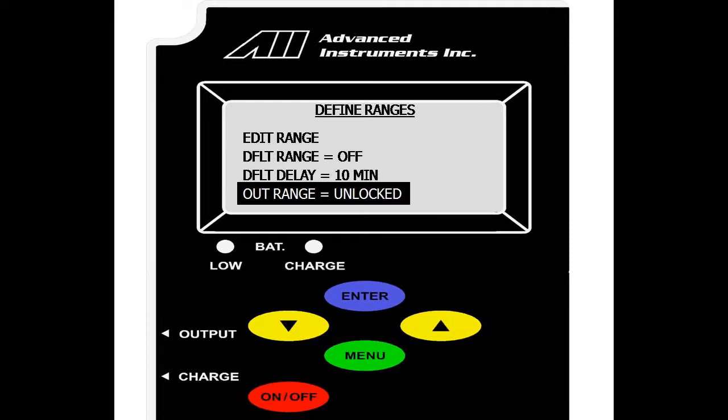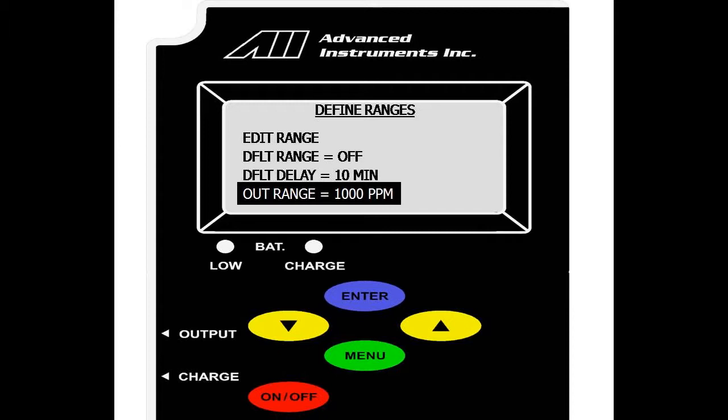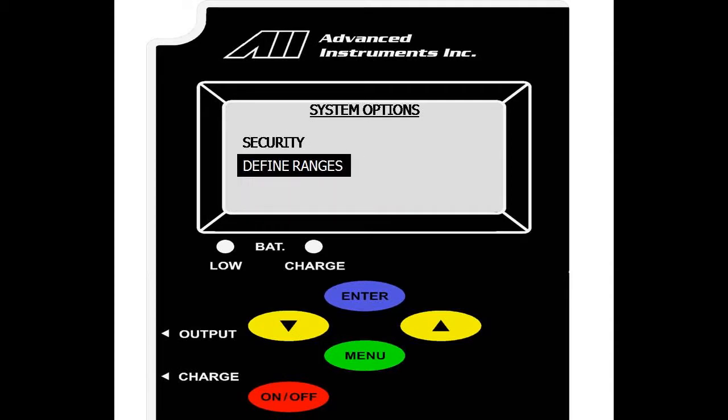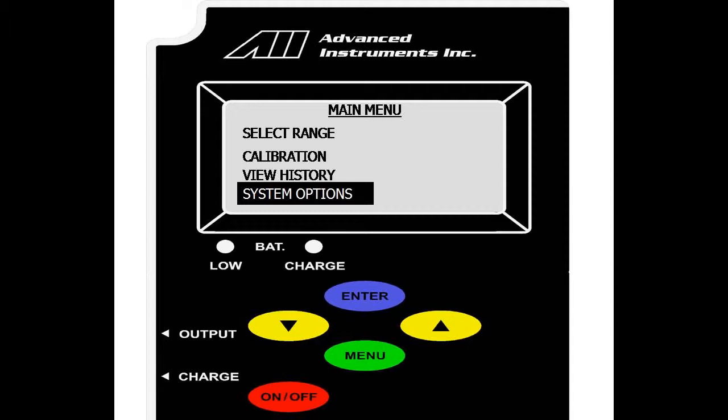And we also have an out of range option. This is your output value and is currently unlocked which means it is set to the current range the analyzer is in. However, you can lock your range at say 1000 parts per million and have your output stay at 1000 parts per million despite what the value is shown on screen. Again, enter to scroll through the various ranges. We are now back to the main menu and that was system options.